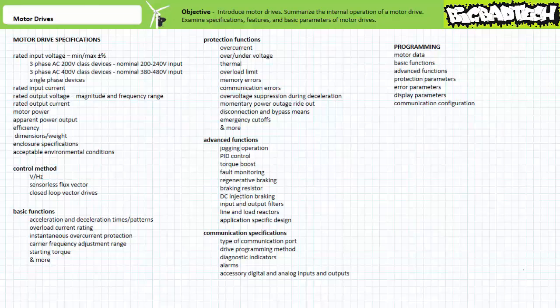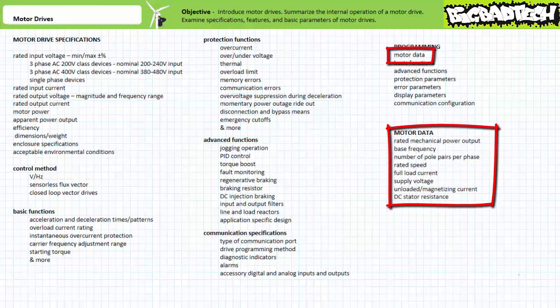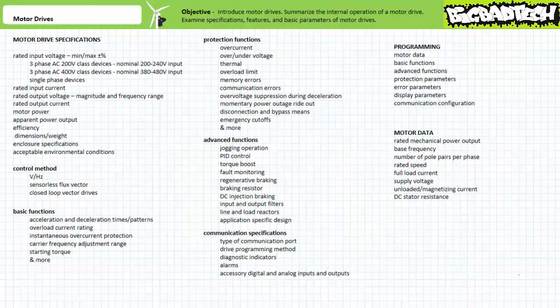A properly pre-configured motor drive consists of a number of user-adjustable parameters that vary from manufacturer to manufacturer and drive to drive. I tend to break parameters into several broad categories: motor data, basic functions, advanced functions, conditions necessitating protection, conditions that warrant errors, parameters that need to be displayed or recorded or sent, and communication configuration. Up front, a motor drive needs to be told what type of motor it's driving. Often this simply necessitates a technician read the motor's nameplate and input the data — including rated mechanical power output, base frequency, number of pole pairs per phase, rated speed, full load current, supply voltage, and depending upon the specific drive and application, unloaded or magnetizing current and DC stator resistance.